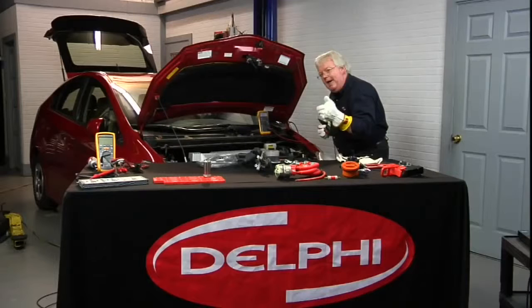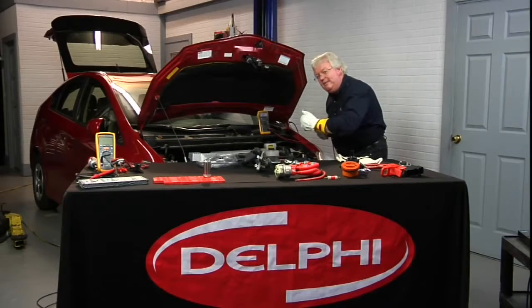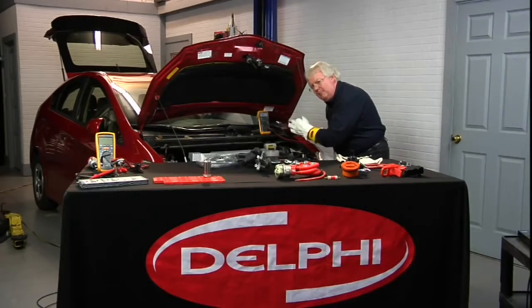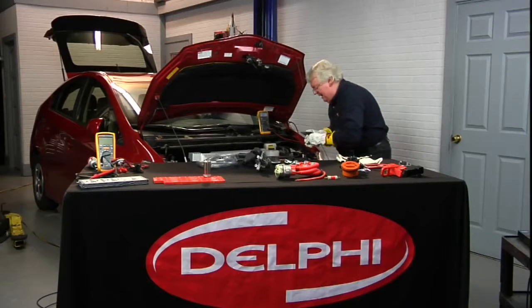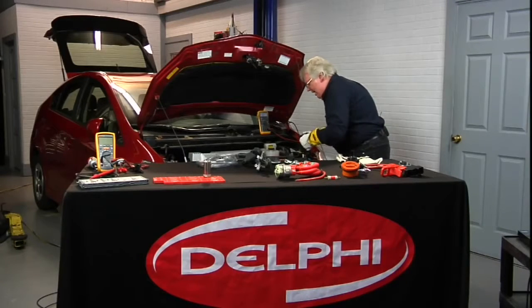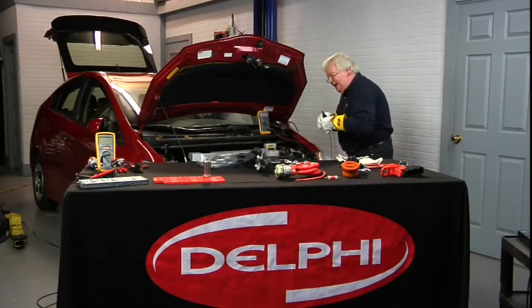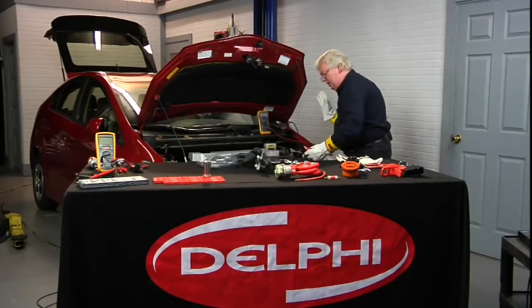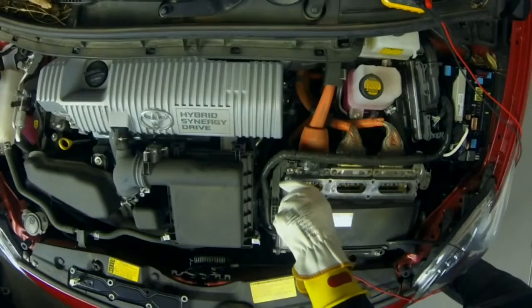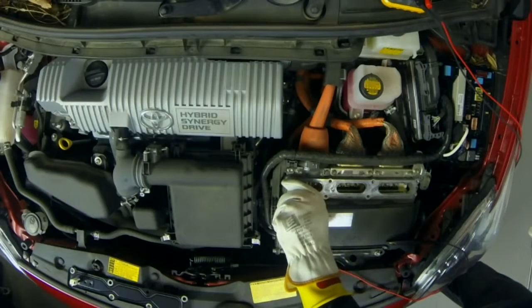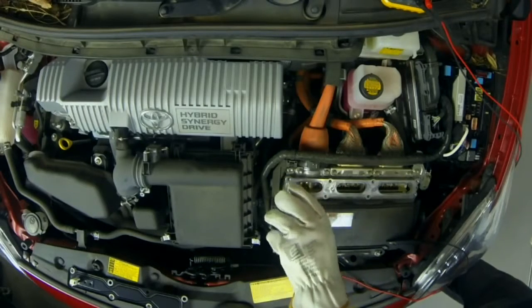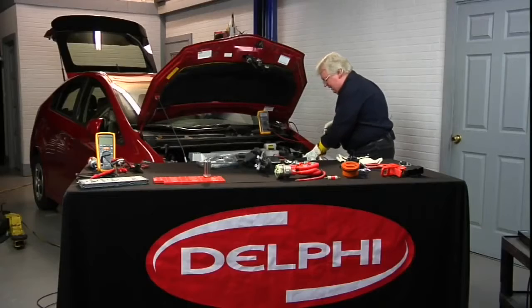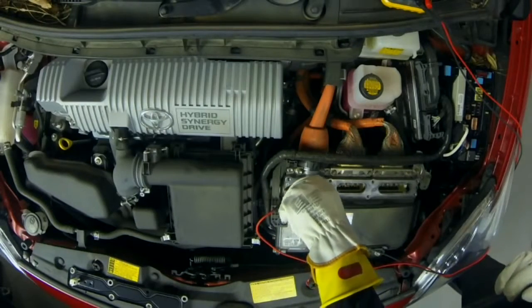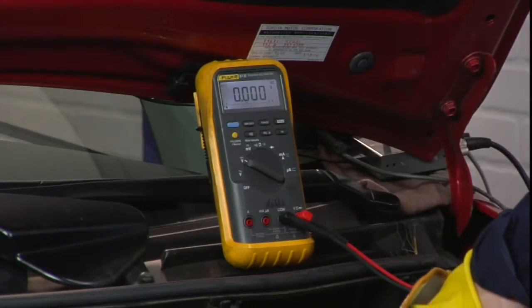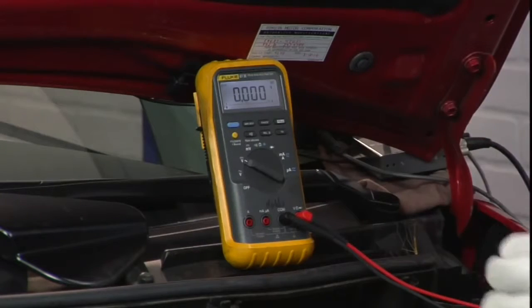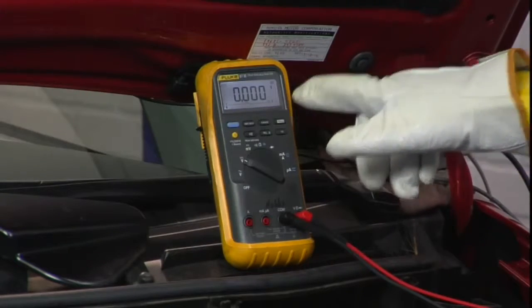That's your power and your negative, positive and negative, 200 and some volts from the battery pack if it were turned on. It's not. But to make sure it's not, I'm now going to, one at a time, one hand out, one hand in, perform the other part of the live dead live test. This would be the dead test, hopefully. So now the other hand is out, one hand is in. Now we have good connection. We have 0.0 volts on the meter.